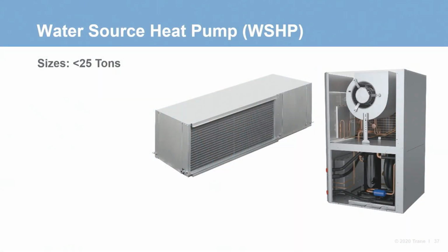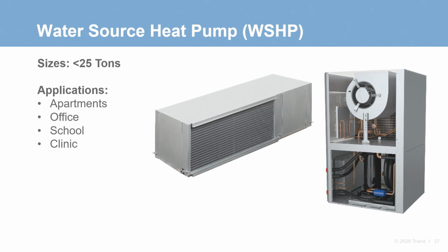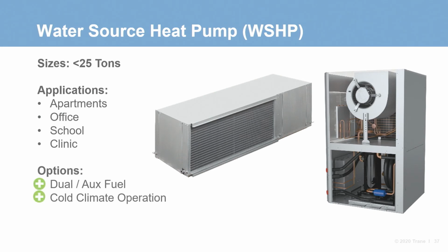Water source heat pumps are probably the most well-known heat pump technology on the market today. Typically, sizes are less than 25 tons and can heat and cool multiple zones or single zones. They cover a wide variety of applications, some of the most common being apartments, offices, schools, and clinics. For electrification options, the system can offer multiple forms of dual fuel. The product itself can be supplied with electric resistance backup heaters.